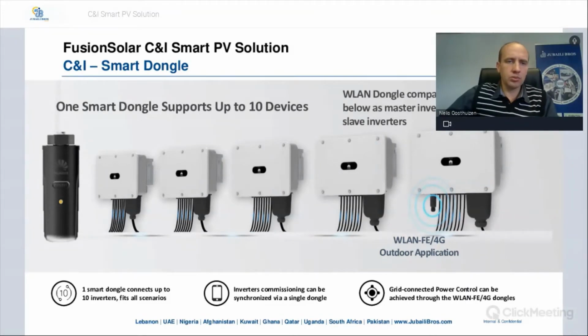Then on the next one, we've got the communication C&I smart dongle. So one smart dongle device can communicate with up to 10 devices. The WLAN dongle is compatible with the 40 KTL and below as a master inverter, and any inverter as a slave inverter. So as I've said, one dongle can support up to 10 inverters. Inverter commissioning can be synchronized via a single dongle, so you can only do setup or commissioning on the master inverter, and then it will relate all of that information to the rest of the slave inverters. Grid connected power control can be achieved through the WLAN FE or 4G dongles.